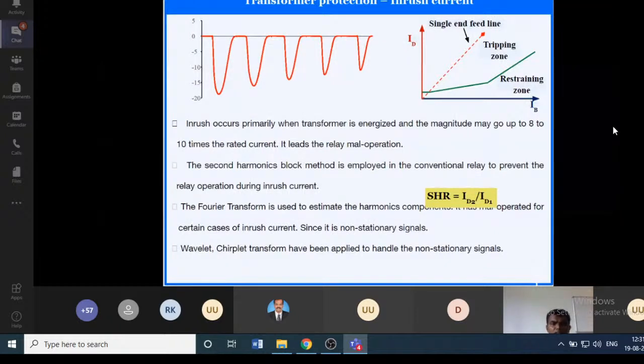The second harmonic component is estimated by Fourier transform techniques. So we can estimate the second harmonic ratio, that is the ratio between the second harmonic component and the fundamental harmonic component. When the second harmonic ratio exceeds a certain threshold value, we can conclude that there is a presence of inrush current, so the relay operation can be blocked.